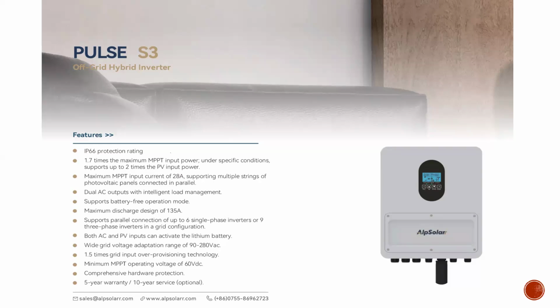So what does that mean? That means you are going to have more solar harvest, unlike some other systems where the minimum MPPT operating voltage is around 120. I know some inverters whose minimum operating voltage is 120, some 150, but as low as 60 VDC, this system is working perfectly fine. And of course, it has comprehensive hardware protection. It's an IP66 system, so it is well built to withstand the harsh temperature and harsh weather conditions of being outside. That is why we can guarantee a 5 years warranty on this system.